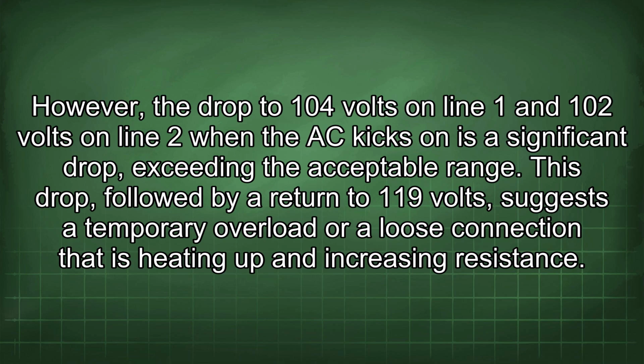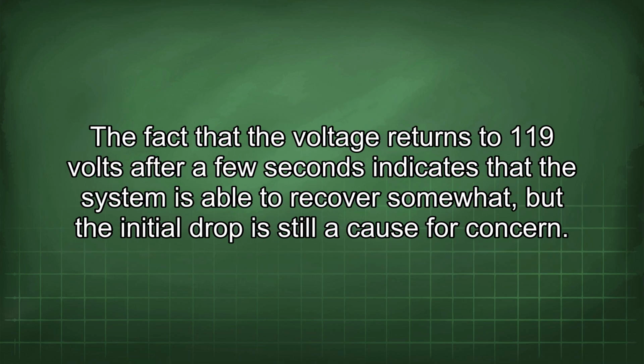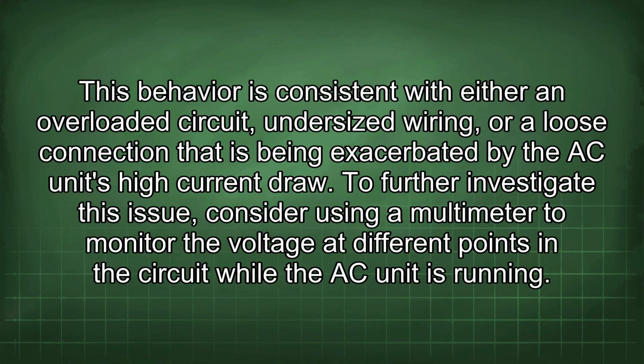This drop, followed by a return to 119 volts, suggests a temporary overload or a loose connection that is heating up and increasing resistance. The fact that the voltage returns to 119 volts after a few seconds indicates that the system is able to recover somewhat, but the initial drop is still a cause for concern. This behavior is consistent with either an overloaded circuit, undersized wiring, or a loose connection that is being exacerbated by the AC unit's high current draw.